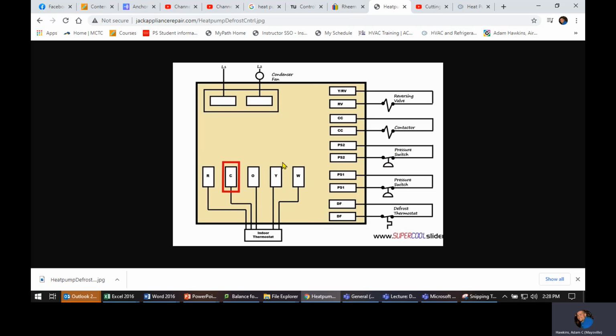So in this case, if I had power coming into yellow and then I didn't have power coming out to the contactor, one would assume that it's the board. And we're going to get into that more when we get into troubleshooting, but just to show you how these all work together. But really what it could be doing is opening one of these pressure switches, and the pressure switch is internally wired with that contactor, saying if the switch isn't made, it's not going to let the contactor kick on. So you have to check everything before you just diagnose this board as bad. But assuming the pressure switches are closed, the contactor should kick on and run.